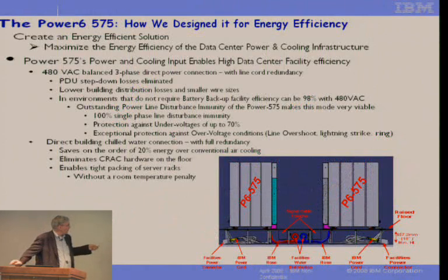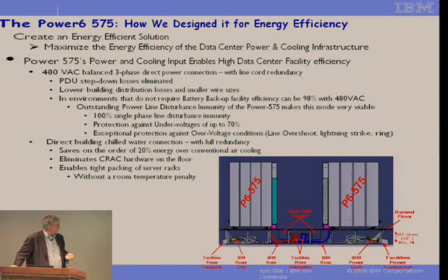I talked about 480, three-phase power connection, line cord redundancy. No PDU losses because we eliminated that. Lower building distribution: if you use 480, you can probably gain 2 or 3 points on a building by using high voltage AC. Direct building chill water, I'll show you this. We save probably 20% on cooling energy by going to liquid versus air cooled, compared to computer room air conditioners that had large blowers and contribute a lot of energy to run those blowers.